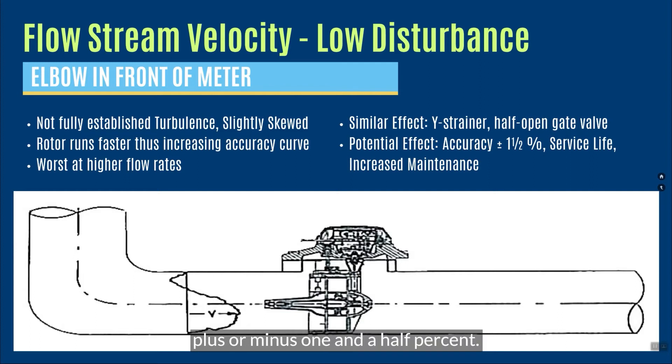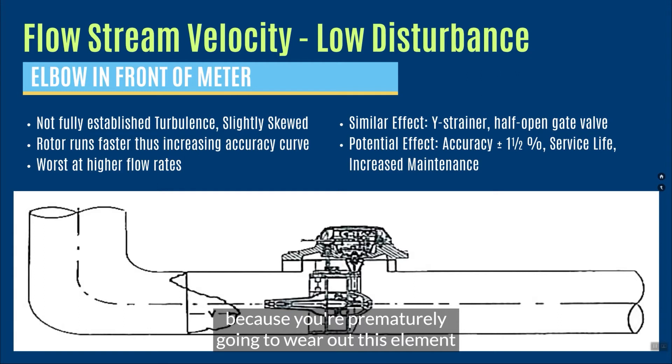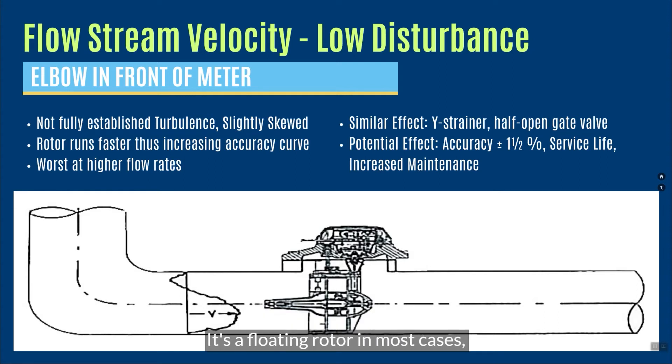This might disturb that accuracy plus or minus one and a half percent. That's revenue. It could also disturb the life of the meter because you're prematurely going to wear out this element because it doesn't have this ideal velocity profile as it approaches it. It's a floating rotor in most cases, and it can be cockeyed by this skewed velocity profile.